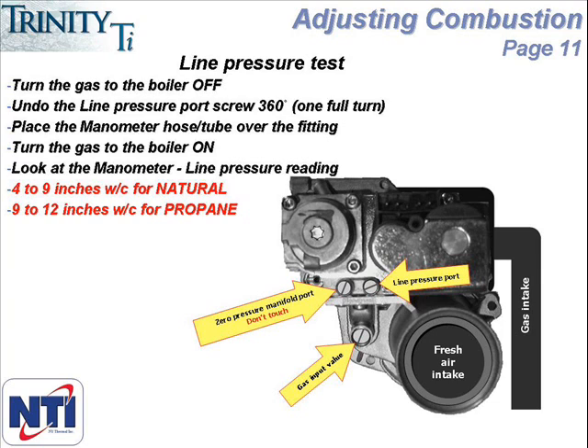You can then place the hose from your manometer over the line pressure port and turn the gas to the boiler back on to take a line pressure reading. It's recommended to leave the manometer in place through the rest of the installation, as you'll need it later to monitor line pressure during ignition.